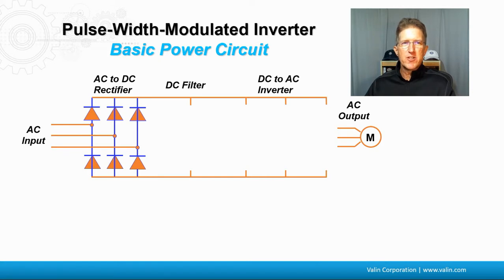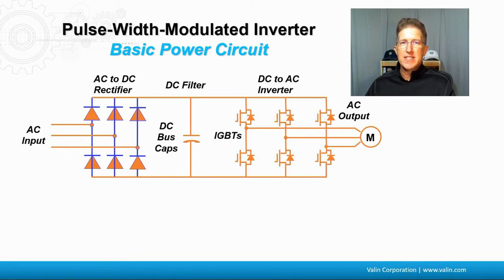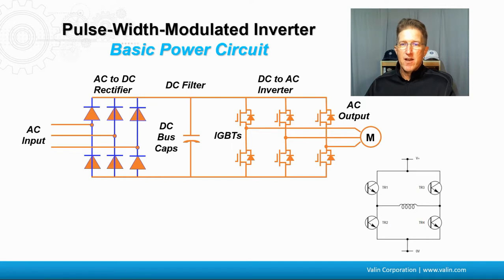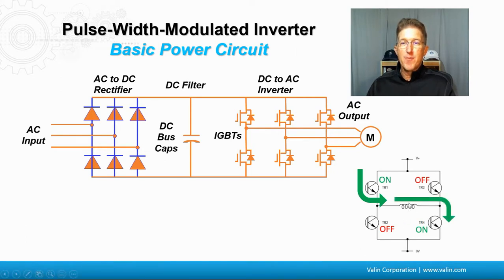Here's what a power circuit looks like for a PWM drive. You have the AC power coming in on the left, it goes through a rectifier, then it gets filtered a bit to help with electrical noise, and then it goes back through a DC to AC inverter. Notice: AC comes in on the left, converts to DC, then back to AC — and it's AC that goes out to the motor. What you see there under the inverter is essentially a series of H-bridges where the transistors are turned on and off in a certain sequence. One coil of a motor is shown: when certain transistors are on, current goes through in one direction; when switched, the current goes back the other way — and that's done per phase of each motor.